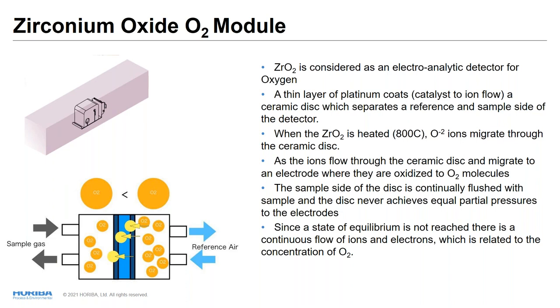Basically, they are trying to strike a balance, because the oxygen concentration of both chambers has to be the same. The zirconium method detects this migration, and it is proportional to the concentration of O2.